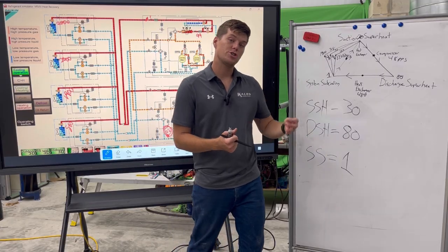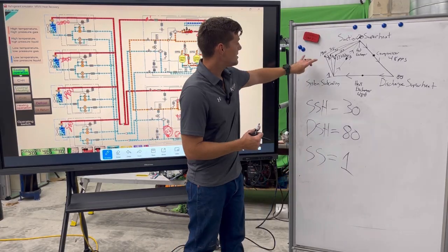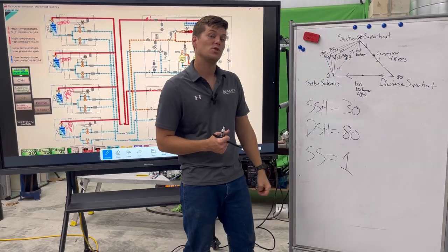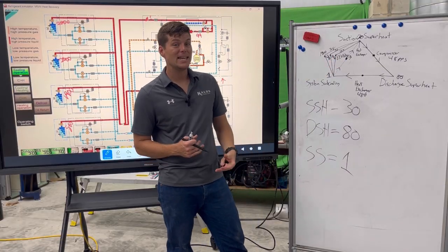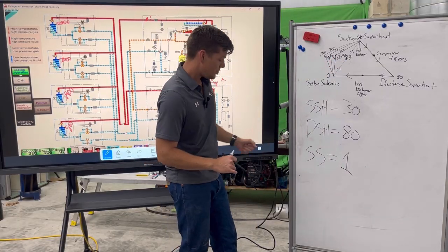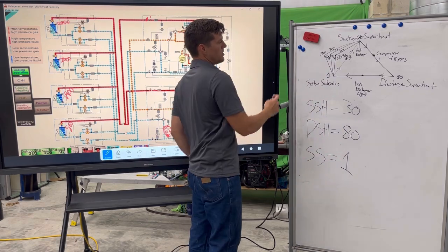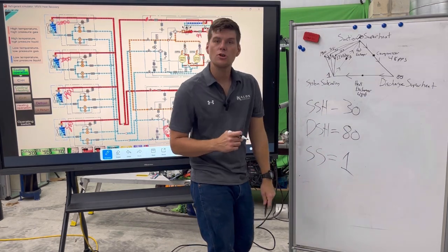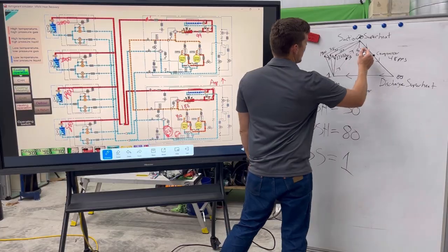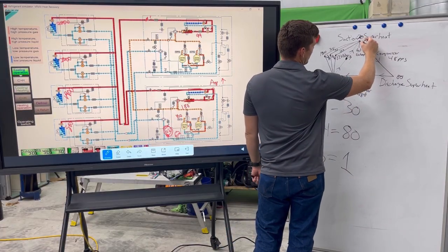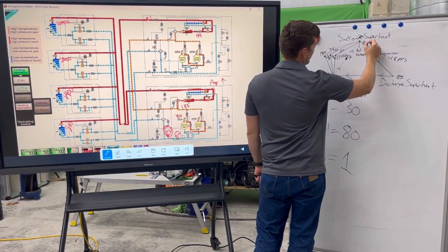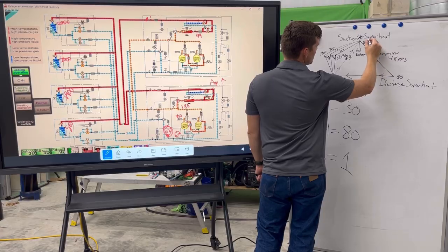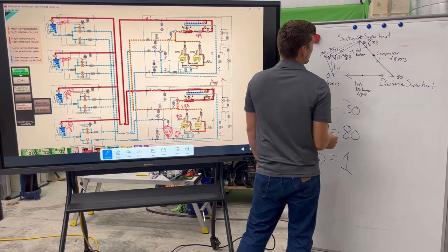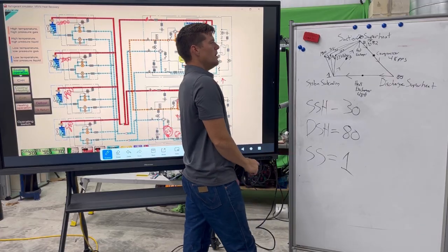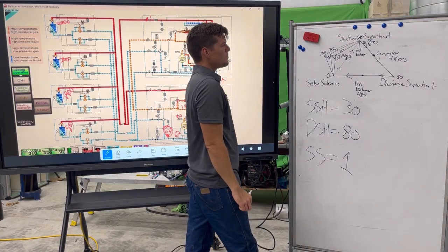It's in a low pressure state, so of course it's going to be close to saturation temperature. That's what it's supposed to be, because remember, it's a liquid slurry, and so it's changing states. So in the process of changing states, now we're going to go through our heat exchanger, and what does it look like on the other side? Well, when I come back over and reconnect all these dots, I find that I'm 80 degrees, 90 degrees, I'm 75 degrees, I'm 82 degrees. That is a huge superheat across my indoor units.